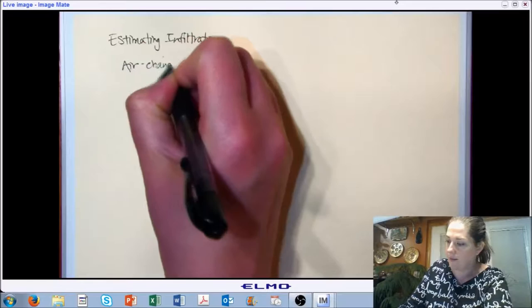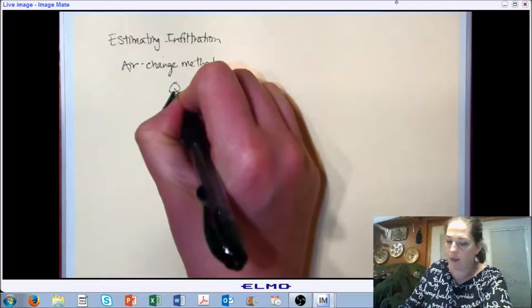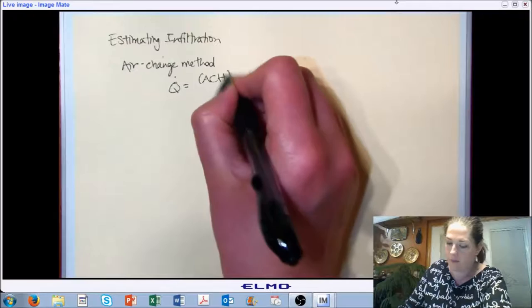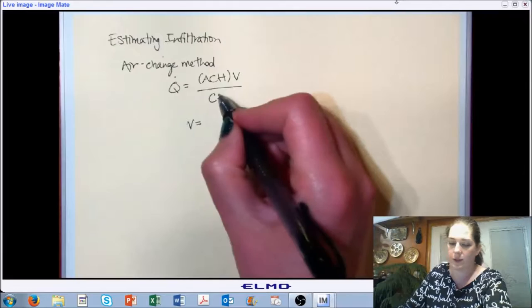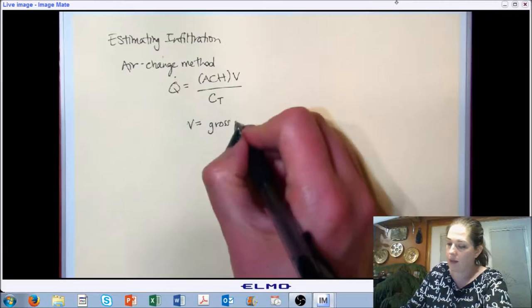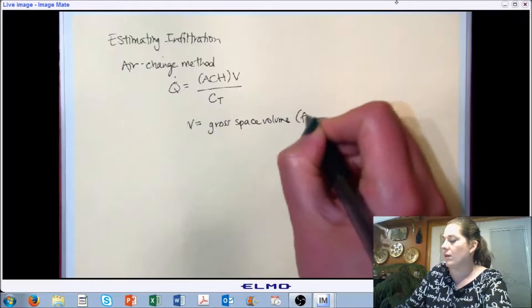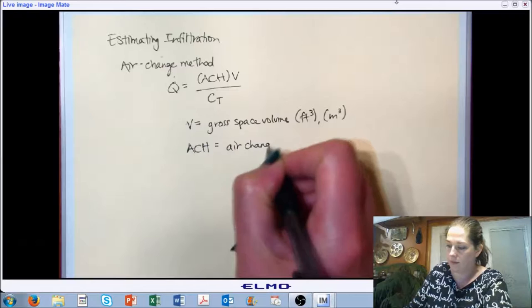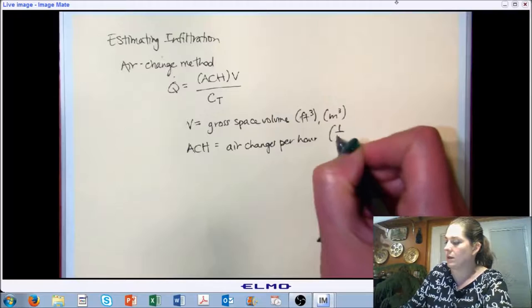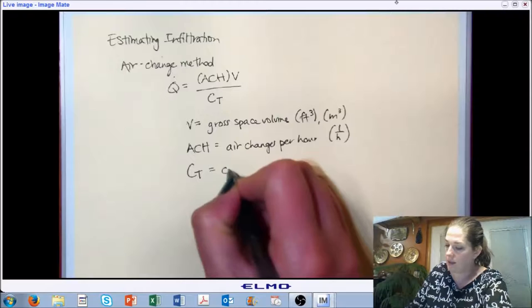The first one is the air change method. In this method, we have an equation where Q equals ACH times V over C_T. ACH stands for air changes per hour. V is our gross space volume, which can be in cubic feet or cubic meters. The units on ACH are one per hour regardless of which unit system you're in. C_T is a constant.